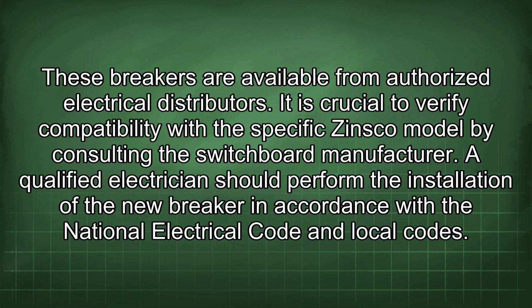These breakers are available from authorized electrical distributors. It is crucial to verify compatibility with the specific Zinsco model by consulting the switchboard manufacturer. A qualified electrician should perform the installation of the new breaker in accordance with the National Electrical Code and local codes.